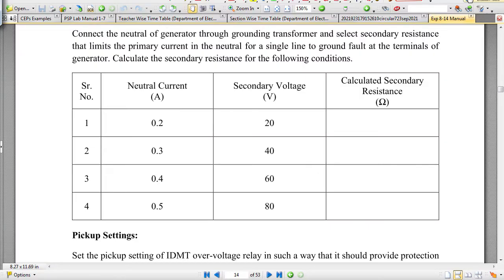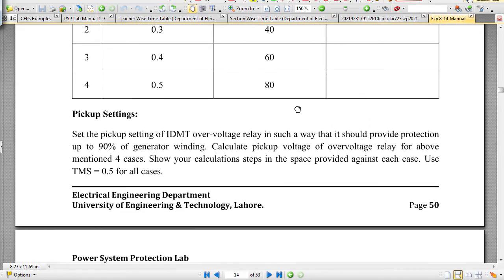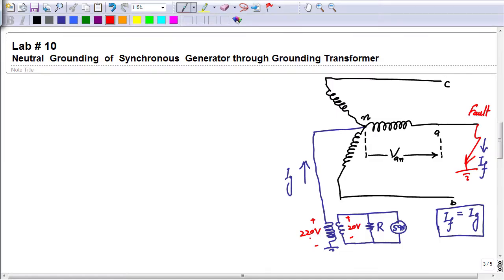If we look at the requirement given in the manual, we will have to set the pickup of this relay in such a way that it should provide protection up to 90% of the generator winding. Now I will explain what is meant by this 90% of the generator winding. Let's assume this grounding transformer turn ratio is 220 volt to 20 volt, and here we have the grounding resistance inserted on the secondary side. If we set the pickup setting of this relay, V pickup or V set, equal to 20 volt, let's see how much portion of this winding will be protected by this setting of this overvoltage relay.